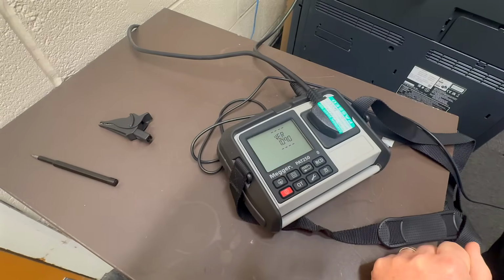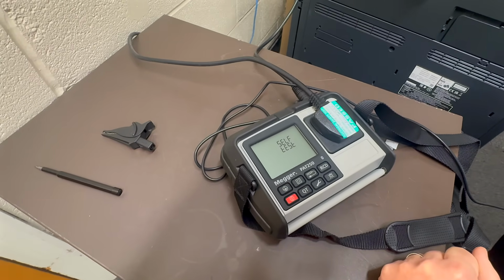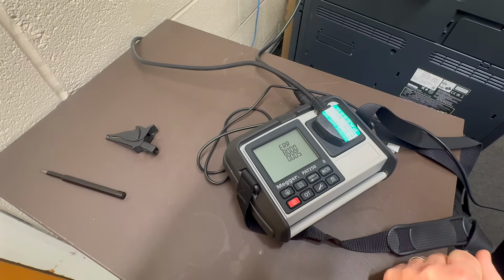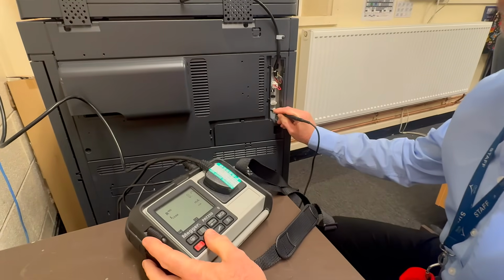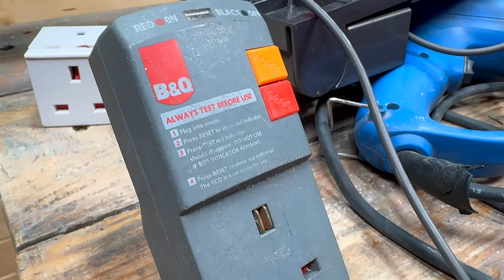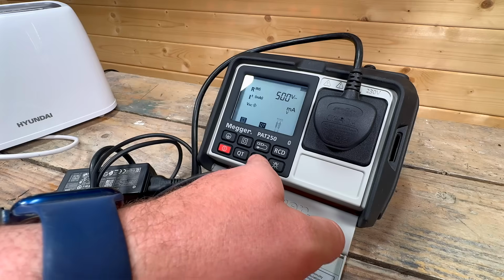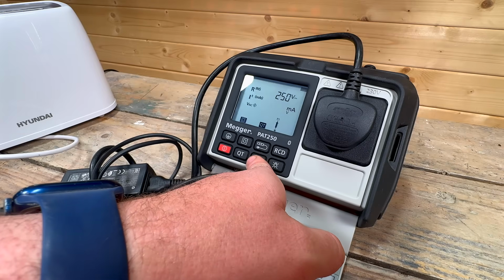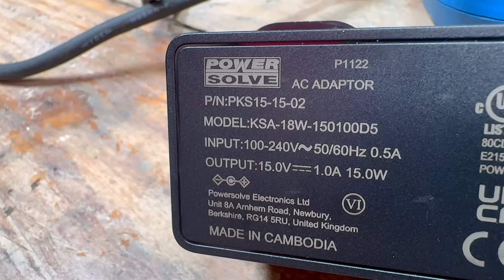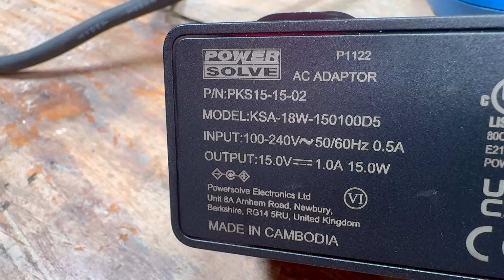It is a dedicated PAT instrument designed to meet the full range of tests required by the code: continuity, insulation, polarity, protective conductor current, touch current and RCD tests. It also supports reduced voltage insulation testing at 250 volts DC for equipment containing filters or surge protection devices.